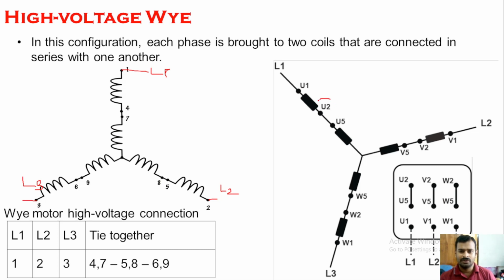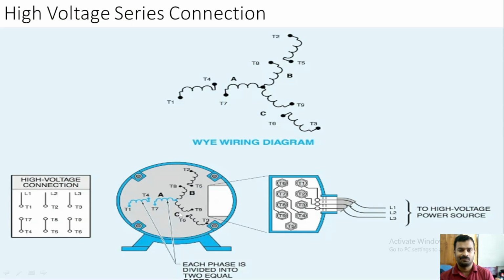So U2 and U5. Different denominations, or different numbering methods, are given here. Here numbering and here lettering are given. U2 and U5 are shorted, V2 and V5, W2 and W5 are shorted. And the connections are given with L1 to U1, L2 to V1, L3 to W1. If this is the case, then it will behave as a high voltage star connected motor. The same thing is given here in the wiring terminal.